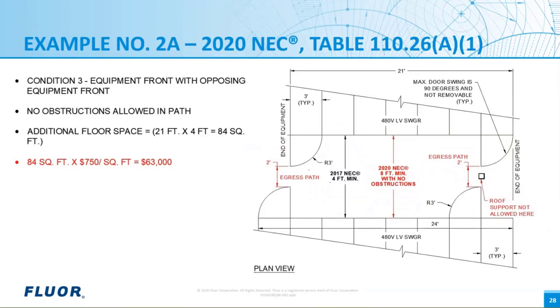The new language in 110.26(C)(2) does not say we need a straight path into and out of the workspace. However, based on the sentence, we could not separate the open doors by 24 inches and put this 6-inch post in that 24-inch space. That would block the 24-inch access to the working space.